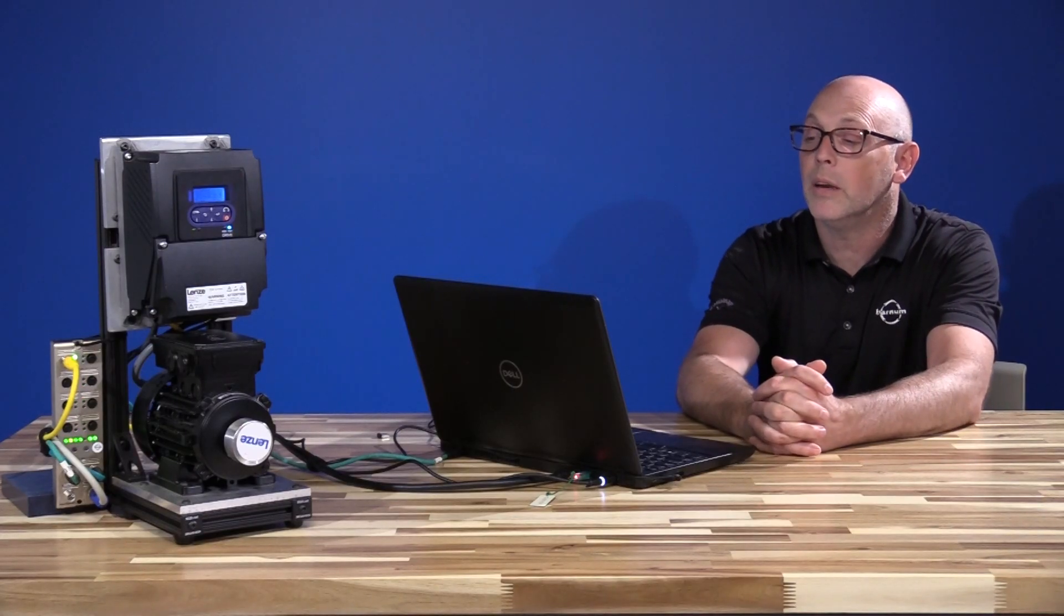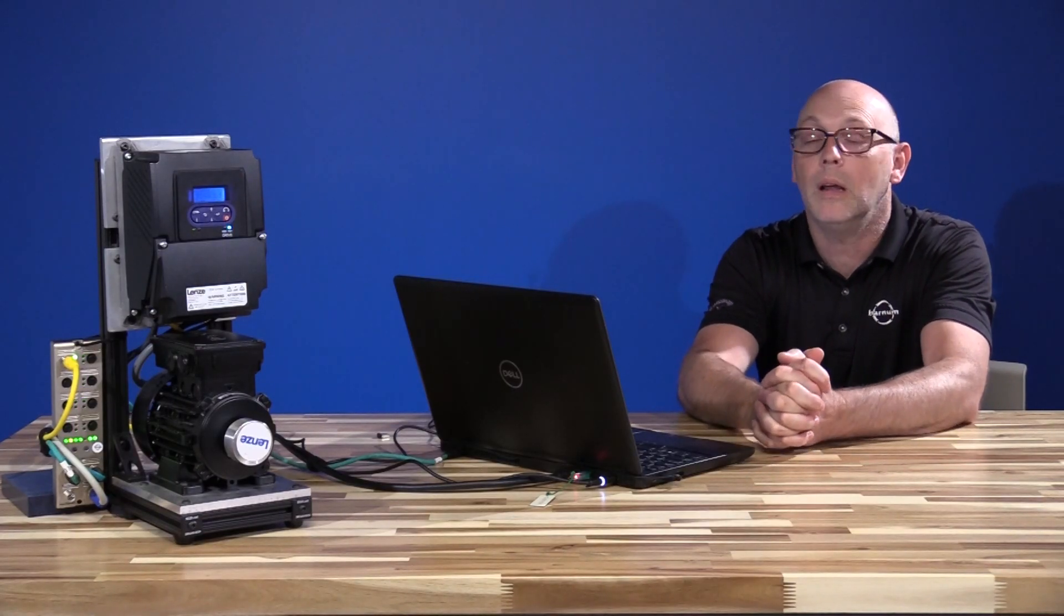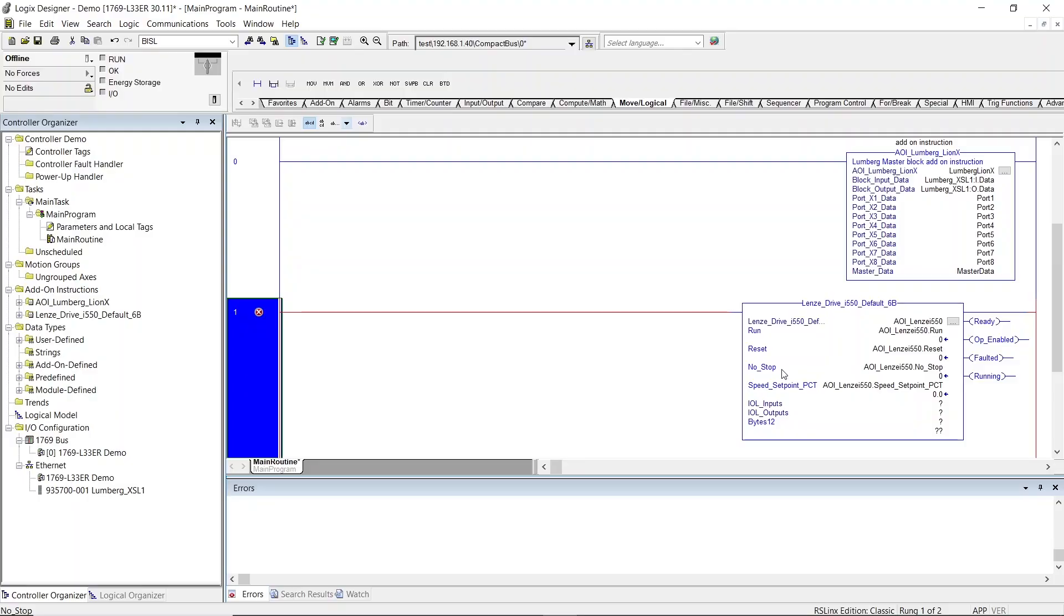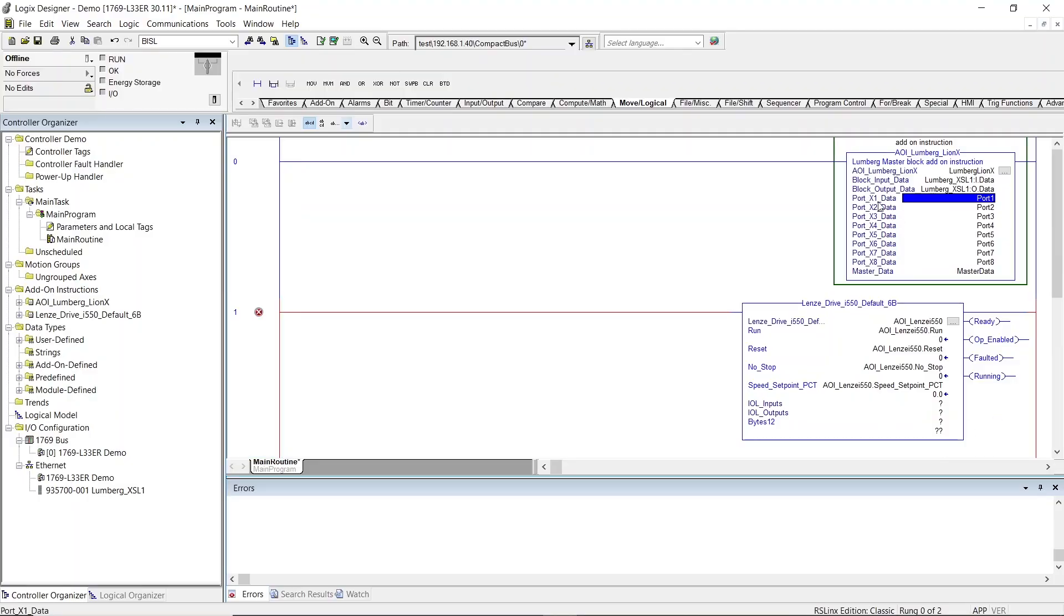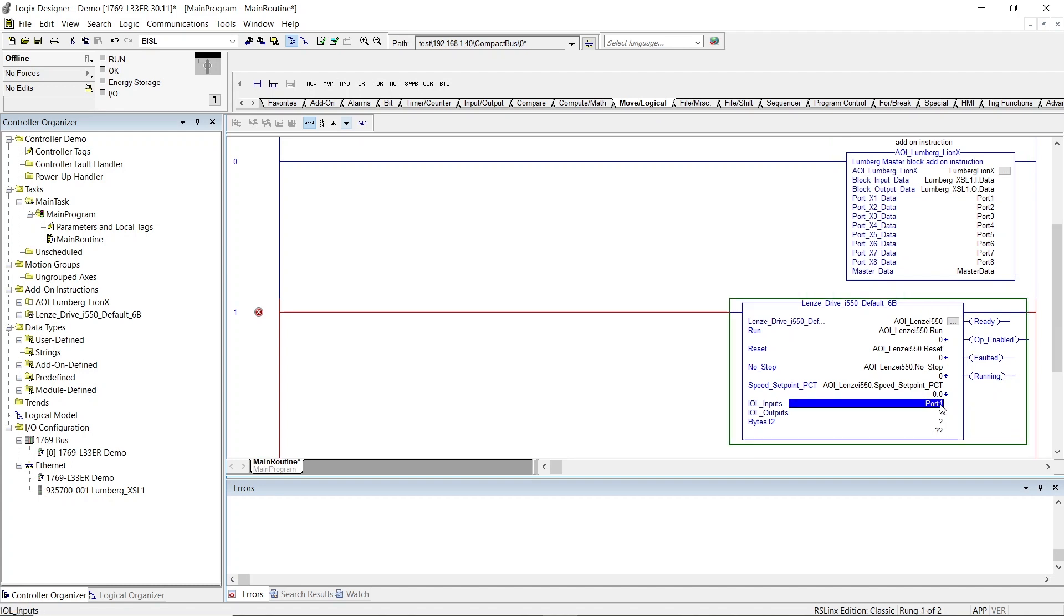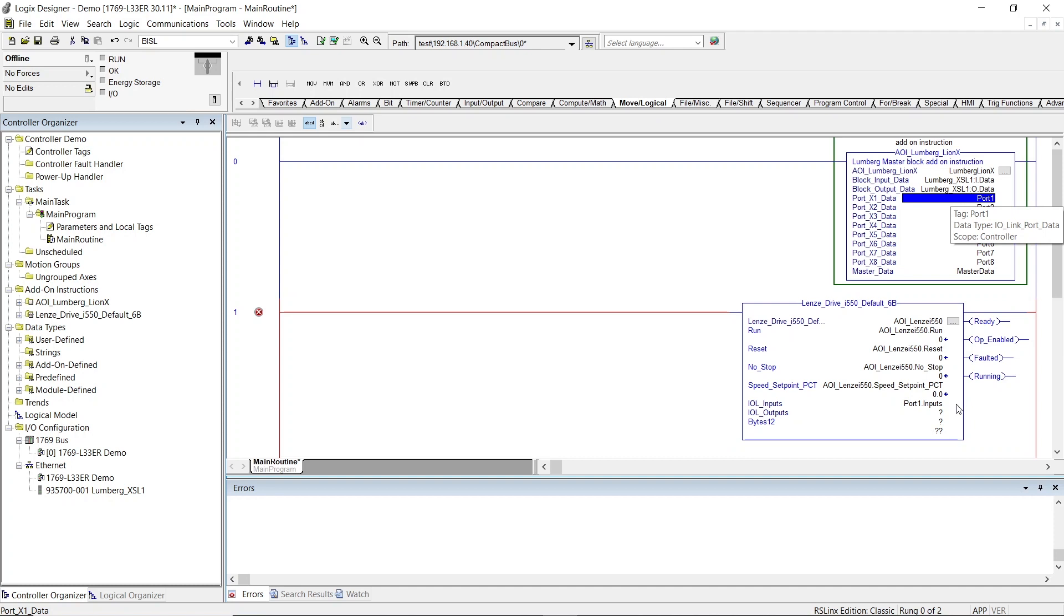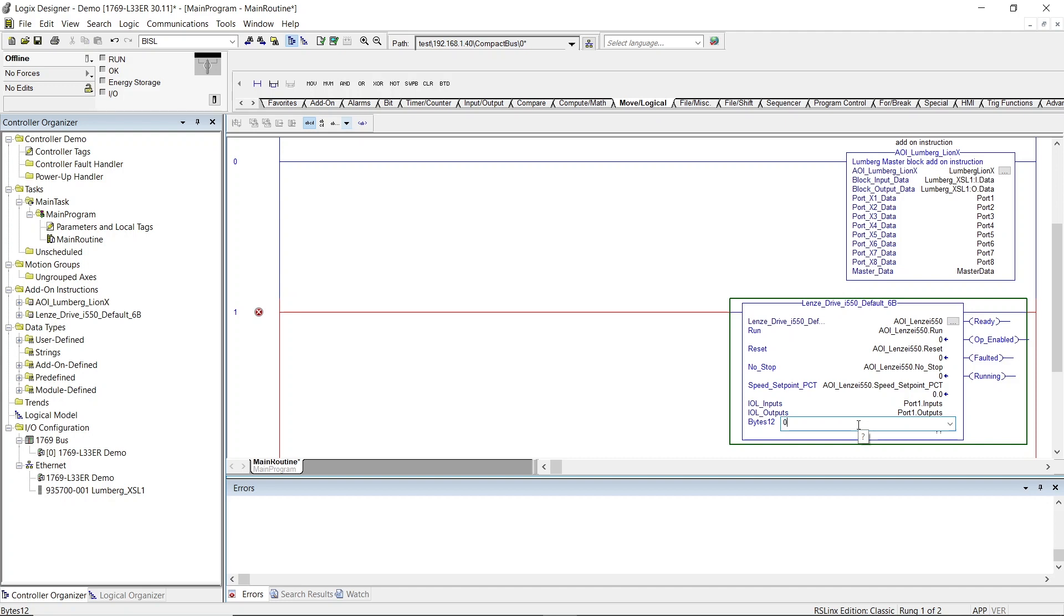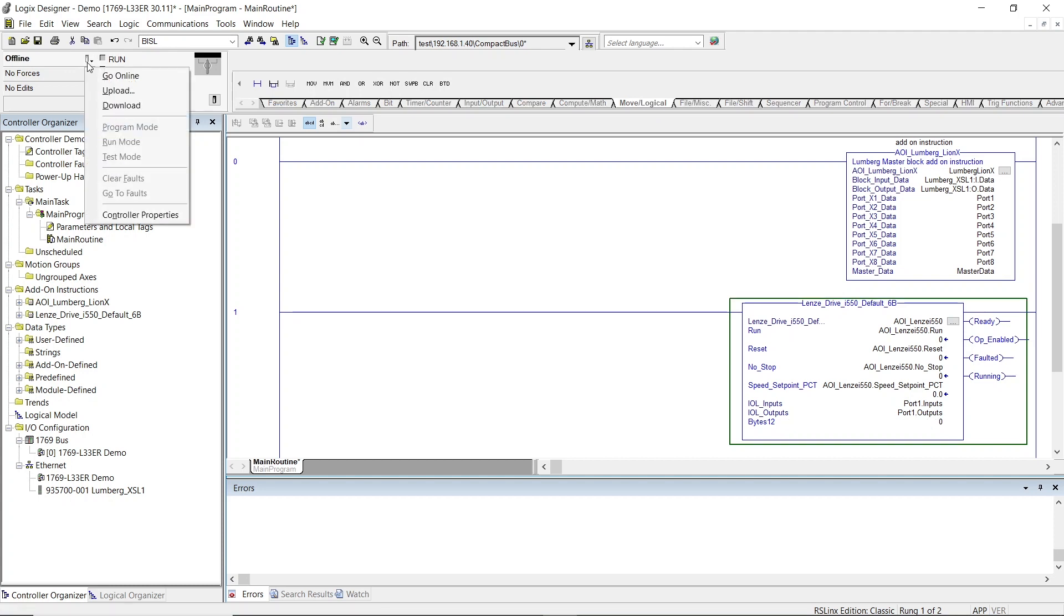Now our drive is plugged into port 1 of the Lumberg XSL Block. So we're going to be using port 1 data from our XSL Block. I'm just going to drag it down onto the inputs, and we're going to specify port 1, and we're going to be using the inputs. And then for the outputs, same thing. Port 1, and we're going to be using the outputs. And the 12 bytes, we're going to be set to zero, because we're actually going to be using six bytes of data. From here, we're ready to download.